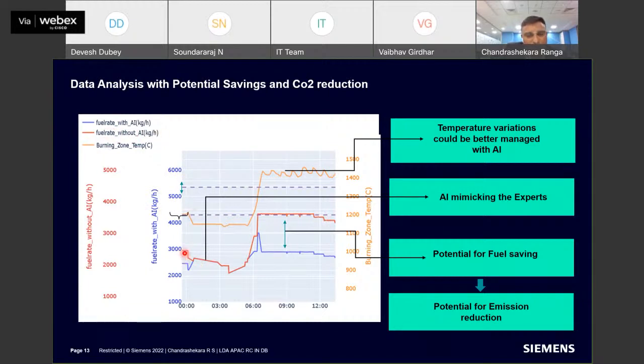How does the fuel rate look? You can see that there is a sudden spike in the fuel rate, and then it comes down, which was not needed. This was set by the operator, not intentionally, but he wanted to bring the temperature up a little into the normal range, and he did not know exactly how much he needed to bring in. So this resulted in a spike of higher temperature. That's what you can see.